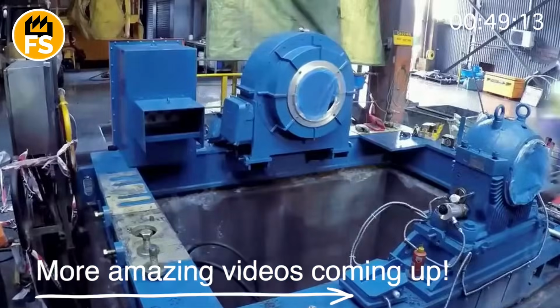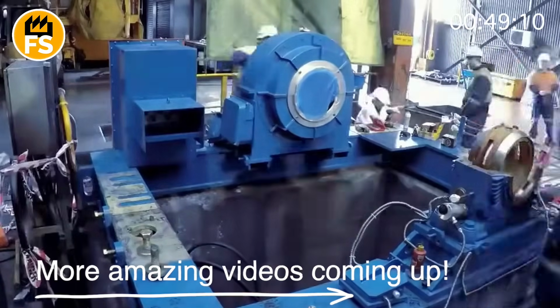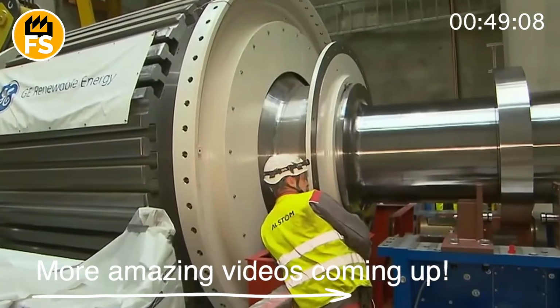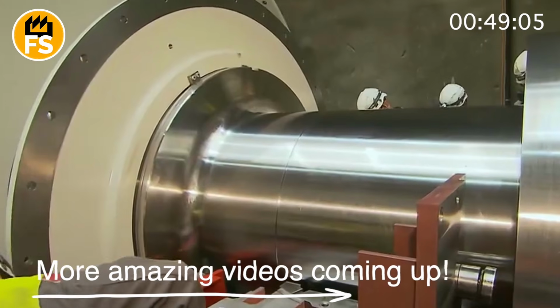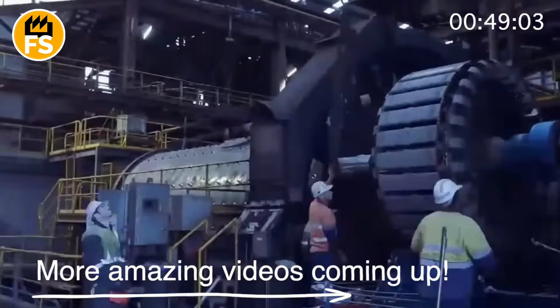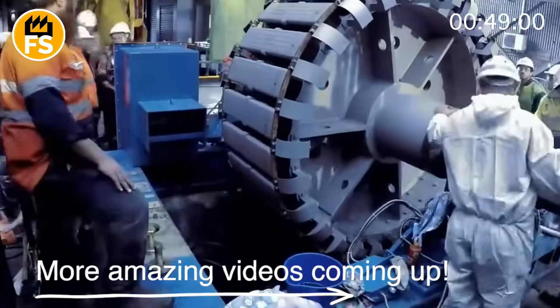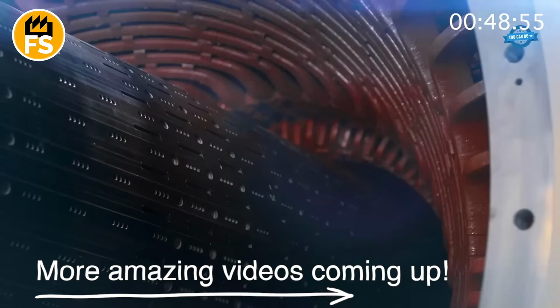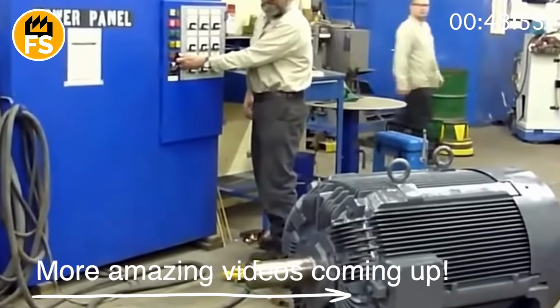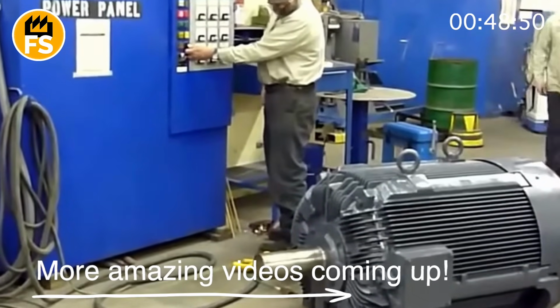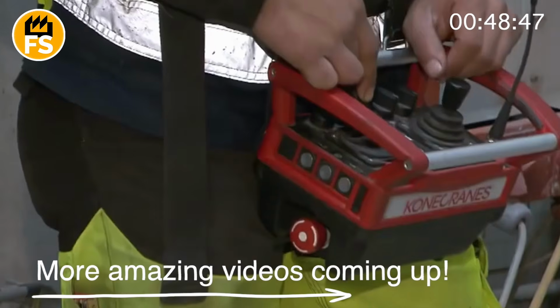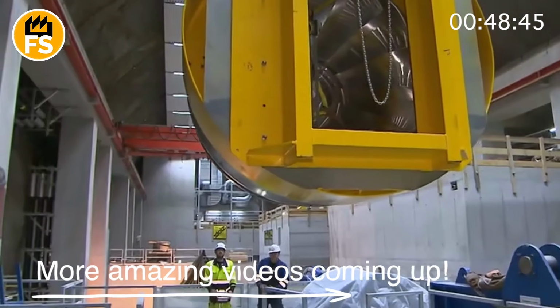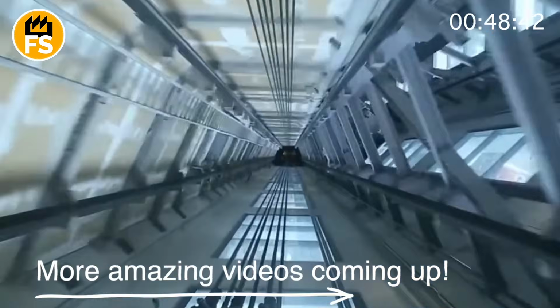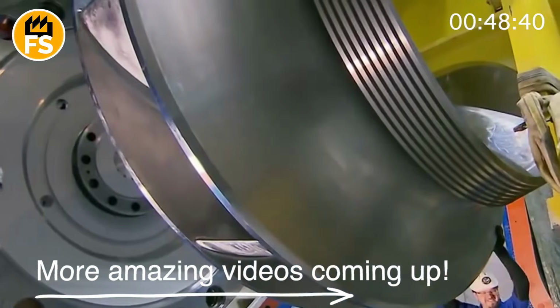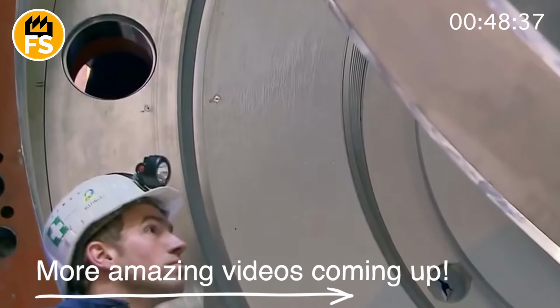The finished motor is sent to the test stand. Here it comes to life for the first time. It's connected to a power supply. Rotations, noise, heat, current consumption are recorded, and efficiency and power are measured. Everything is documented. The motor's passport contains dozens of parameters. If the motor passes all tests, it's packaged, a seal is applied, and an instruction manual is added. And very soon, this motor could be working on a conveyor, in an elevator, or in an electric train, wearing down metal and converting current into motion, without rest for tens of thousands of hours.